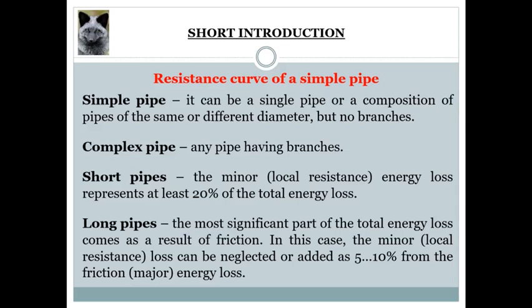Long pipes are those where the most significant part of the total energy loss comes as a result of friction. In this case, the minor energy loss can be neglected or just added as a percentage in the range of 5 to 10% from the friction or also called major energy loss.